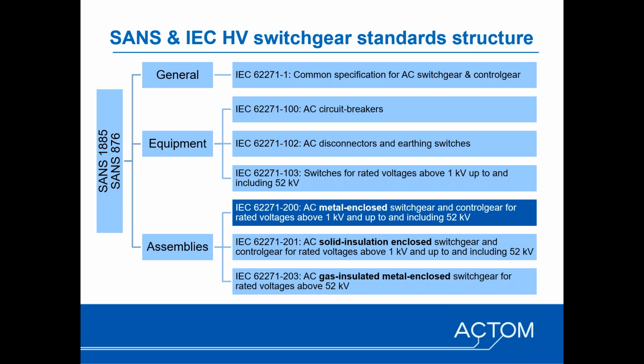And then in the 200 series of the 62271 standard, we've got the assemblies, and most of you might be familiar with the -200, which covers metal enclosed switchgear and control gear up to 52 kV, so effectively medium voltage. Then there's another standard, -201, which is very similar, but the title is AC solid insulation enclosed switchgear, as opposed to metal enclosed switchgear, but also covering rated voltages up to 52 kV.